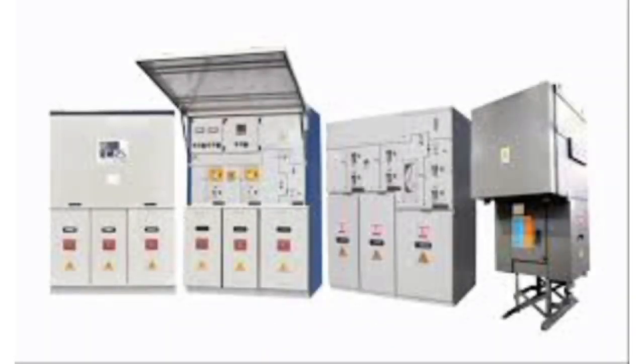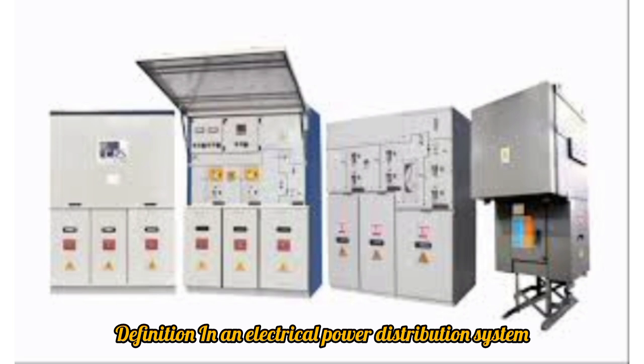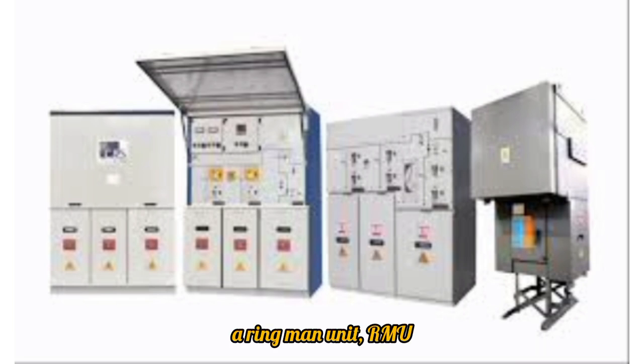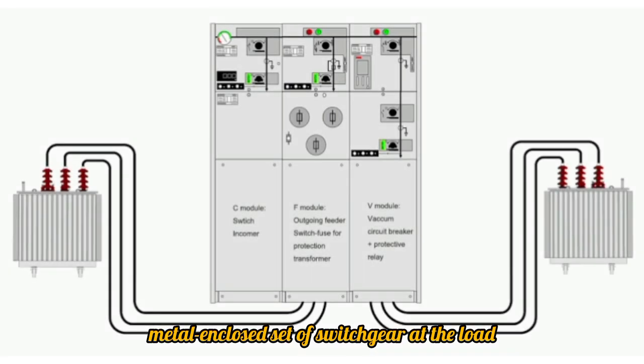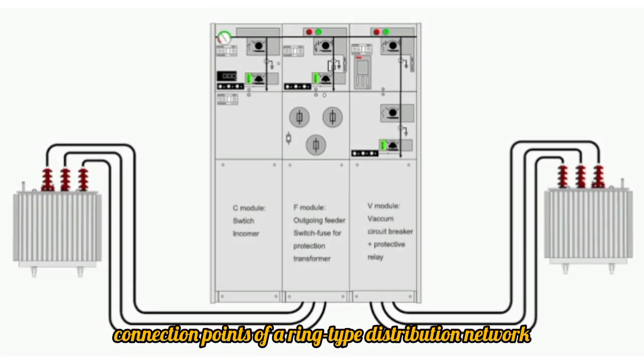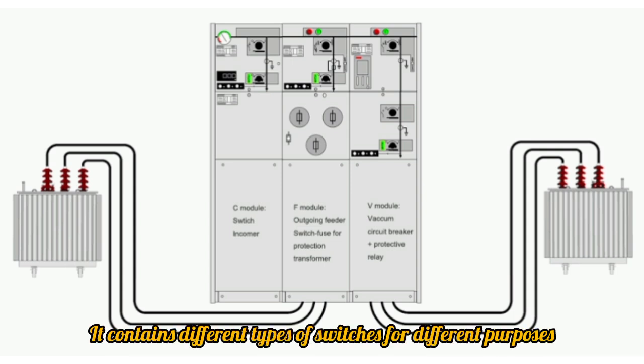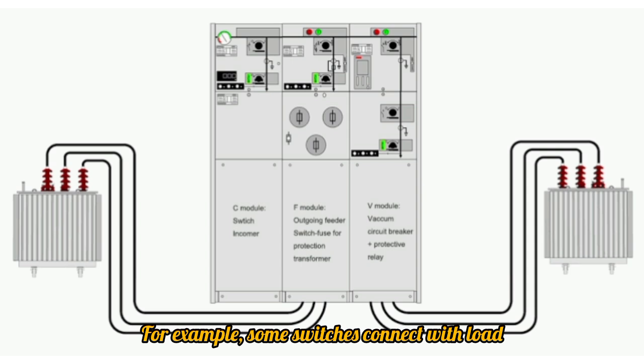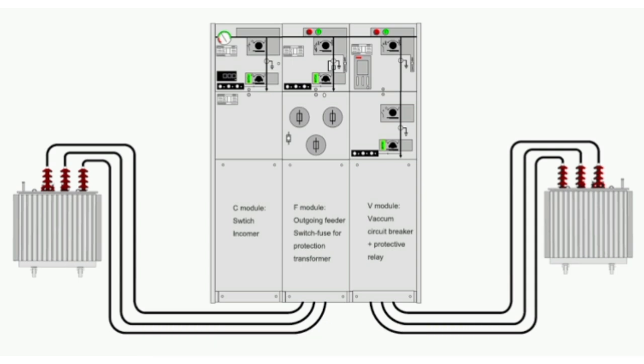Ring main unit. Definition: in an electrical power distribution system, a ring main unit (RMU) is a factory-assembled, metal-enclosed set of switchgear at the load connection points of a ring-type distribution network. It contains different types of switches for different purposes. For example, some switches connect with load, some feed a distribution transformer, etc.